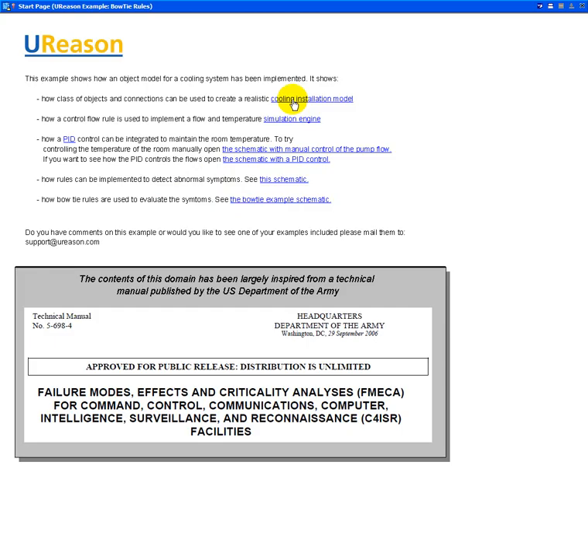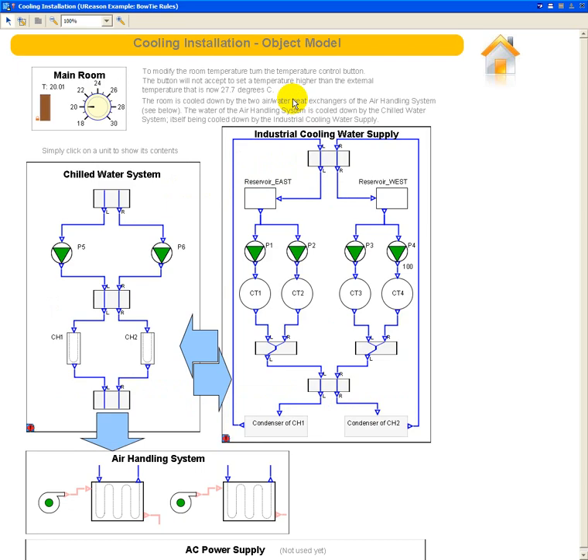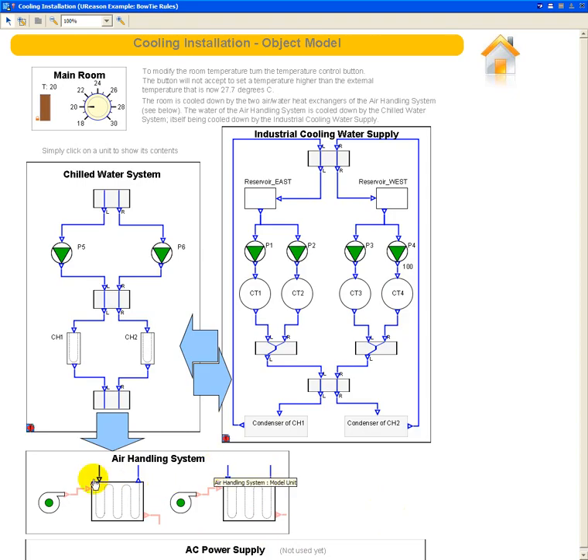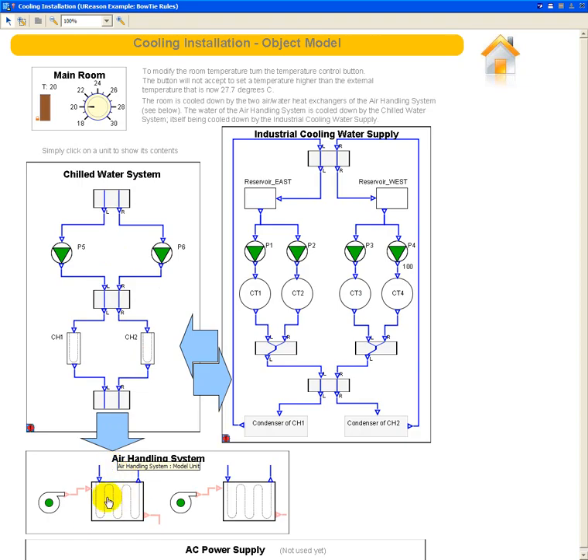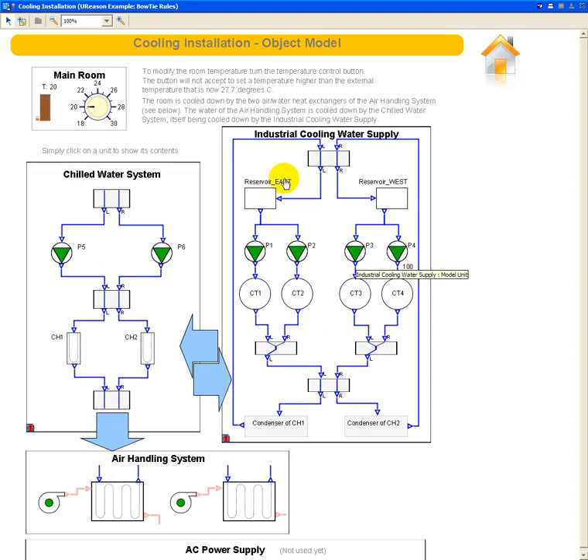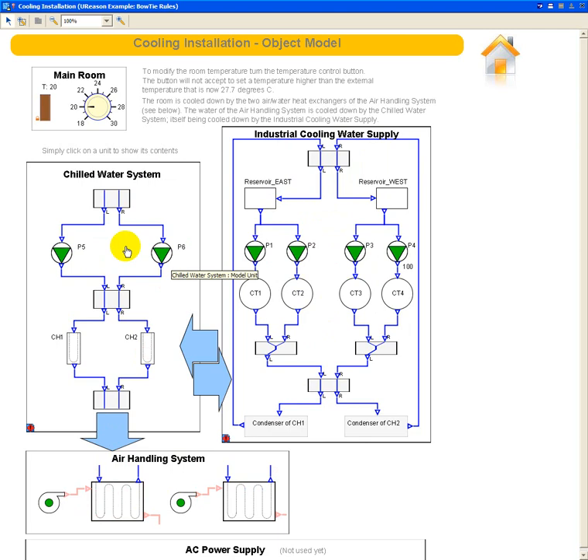So let's first drill into the cooling installation model. As you can see this model consists of several units. We have here at the bottom a power supply unit that's not being used in this demonstration. We then have an air handling system that is there to cool down the air coming from these fans that will flow into the room. We have a chilled water system that is there to cool down the water of these heat exchangers. And then finally we have a last unit here, the industrial cooling water supply unit that is there to cool down the water from the chilled water system.